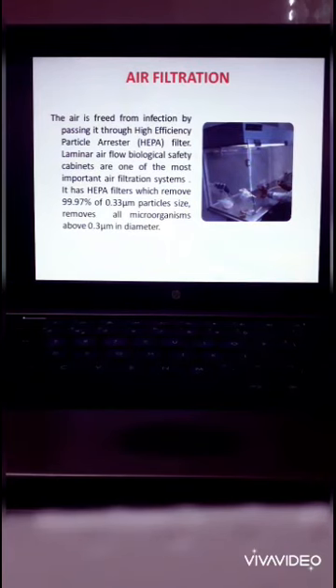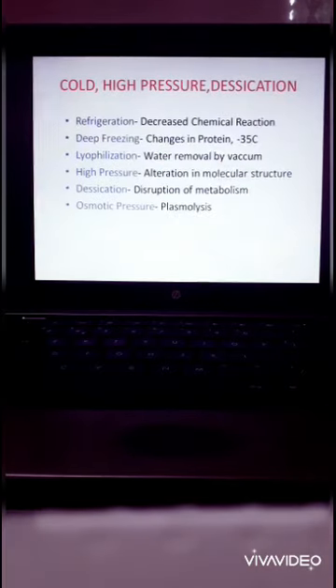Air filtration. In microbiology, the major work is done in an environment which is organism free, so that we can culture the organisms. For that we require the air to be sterilized. How can we sterilize the air? The air is freed from infection by passing it through a high efficiency particulate arrestor, that is a HEPA filter. Laminar air flow biological safety cabinets are one of the most important air filtration systems. It has HEPA filters which remove 99.97% of 0.3 micrometer particles, which removes all organisms above 0.3 micrometer in diameter.